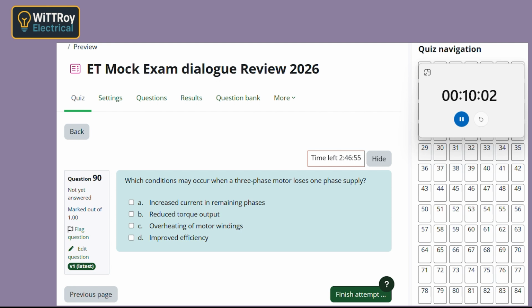Question 90. A 3-phase motor loses 1 phase during operation. What happens? Current increases, torque drops, and it overheats? Yep, that's a really good answer. Let's just connect it. When 1 phase is lost, the motor still tries to run. But it doesn't have full supply. Exactly. So the remaining phases carry more current. That causes heating. Yes, and at the same time, the motor can't produce the same torque. So performance drops and damage risk goes up. Exactly. That's why it's such a serious condition.